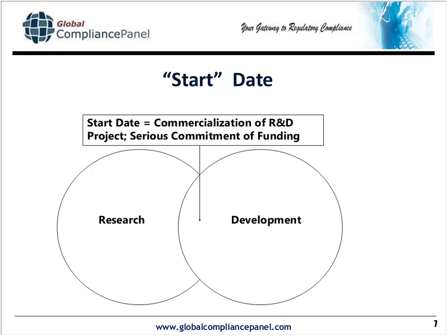So what I tell my clients is it should be at the point where the company decides they've got a blue sky product in R&D that they realize is commercial. And they themselves want to develop it for commercialization, or they themselves want to develop it to a point where they can spin it off or sell it for commercialization. At that point where serious money's thrown at a product that was in R&D to develop it for the commercial market, that is probably the date for your start date for design control. The FDA expects you to define that as a company and then to follow your own definition.